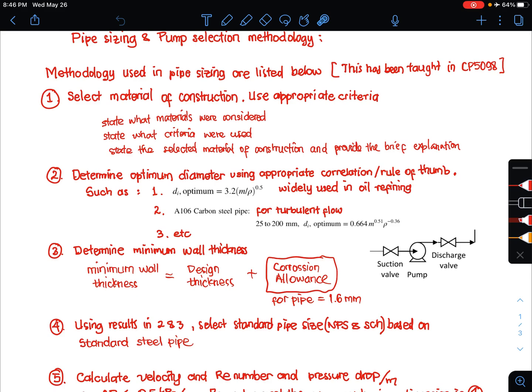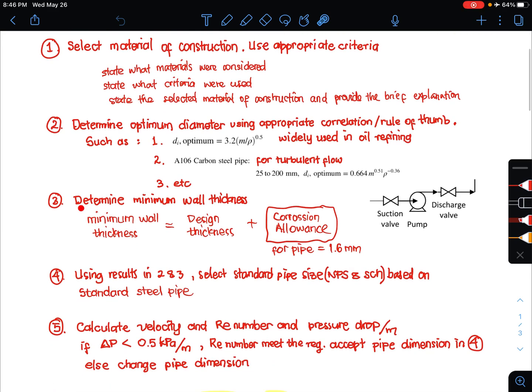The next step is to determine the minimum wall thickness of the pipe. The minimum wall thickness equals the design thickness, which is the thickness required to withstand the pressure difference between inside and outside the pipe, plus the corrosion allowance. In the context of piping, the corrosion allowance is usually 1.6 mm.